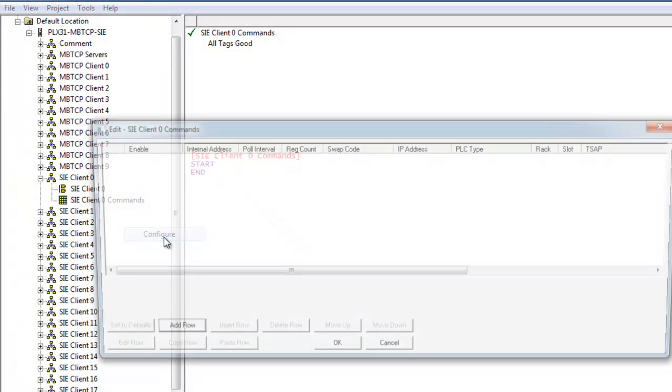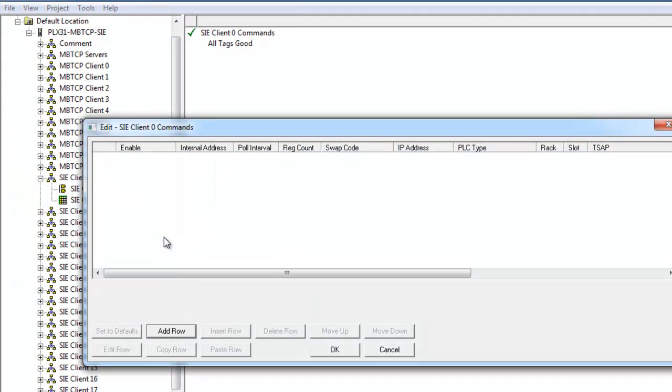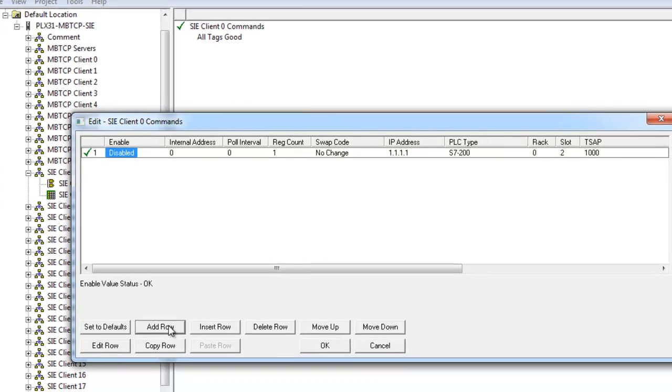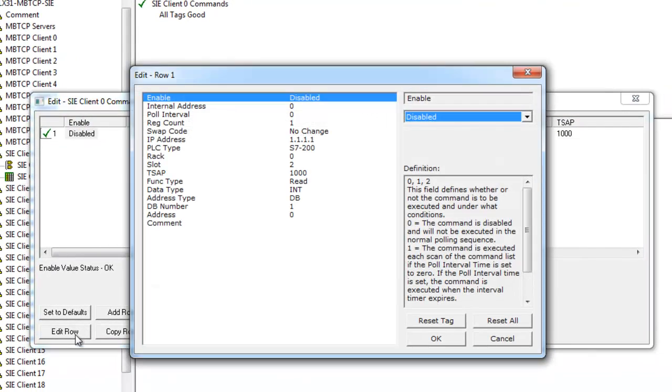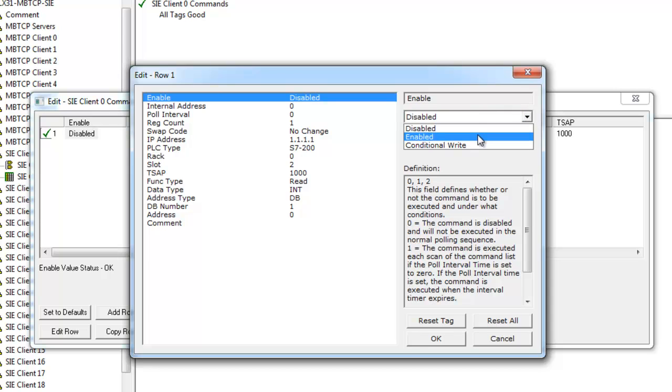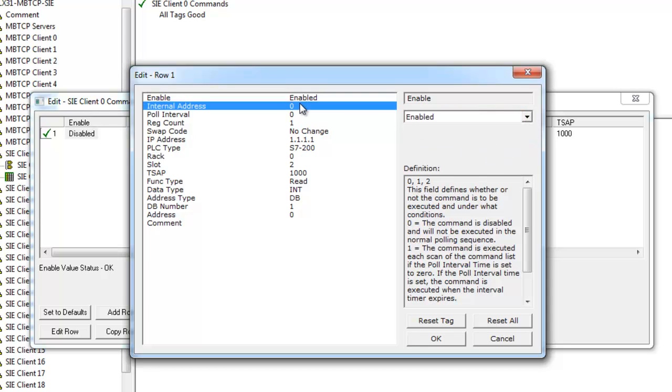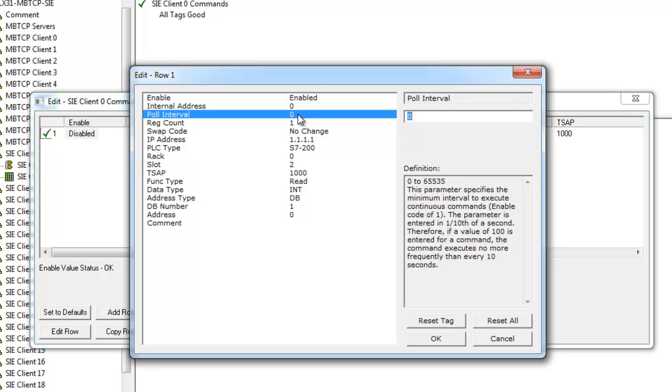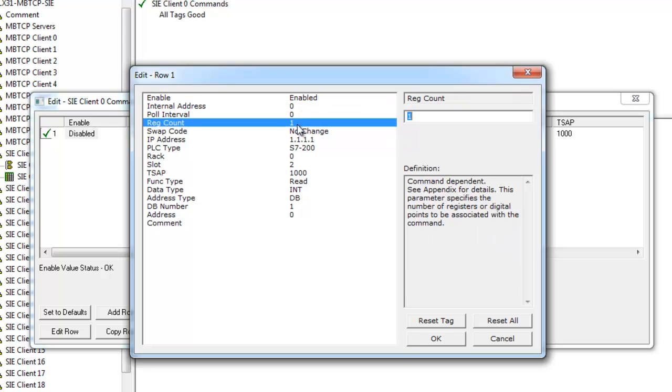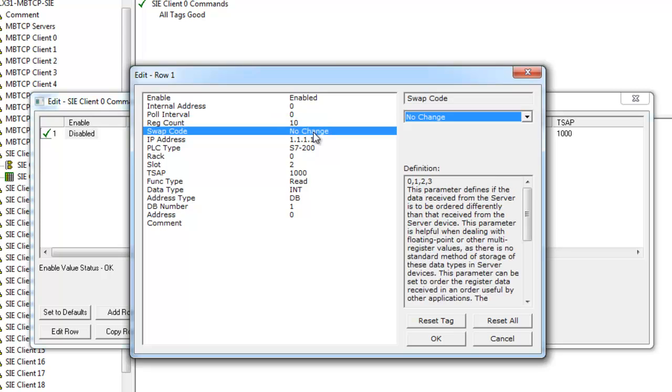Next we're going to configure the SIE client zero command. We're going to add a row and select edit row. First we're going to enable this command. The internal address we'll leave at address zero. The poll interval also at zero. We will change the registers to 20 because we're going to write 20 words to our S7300.